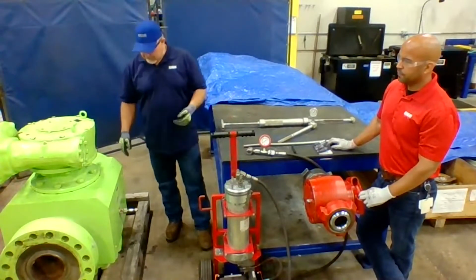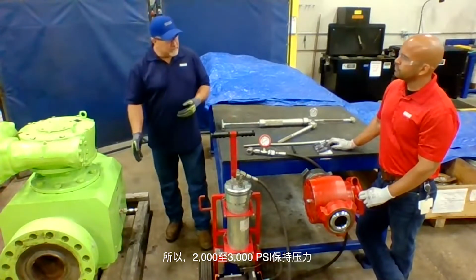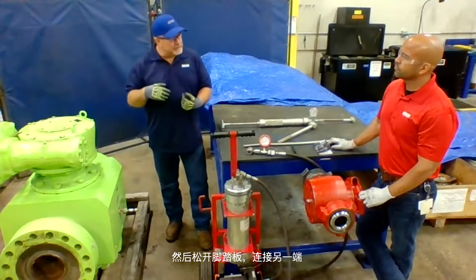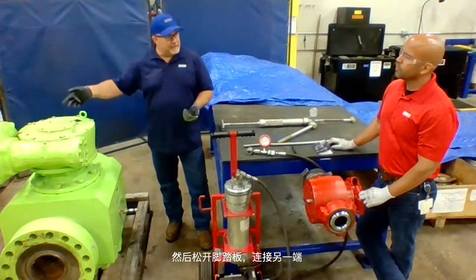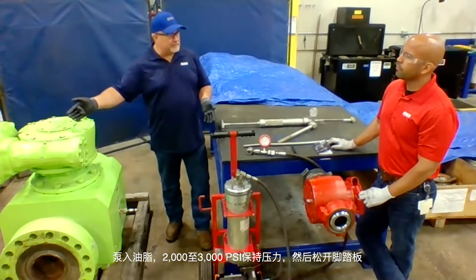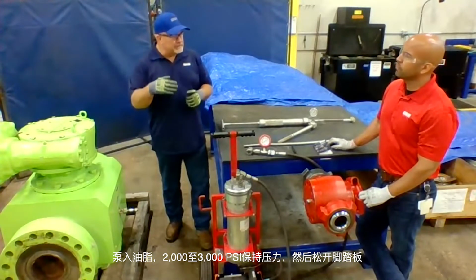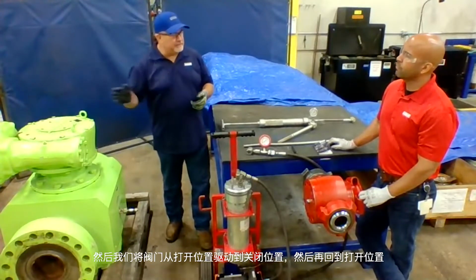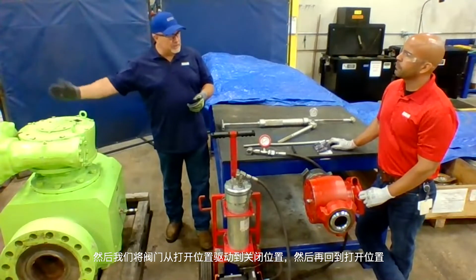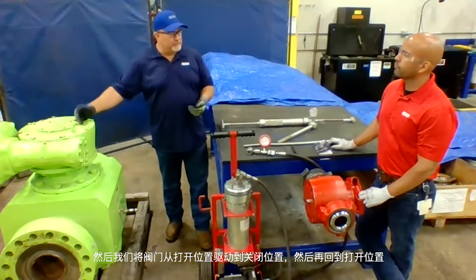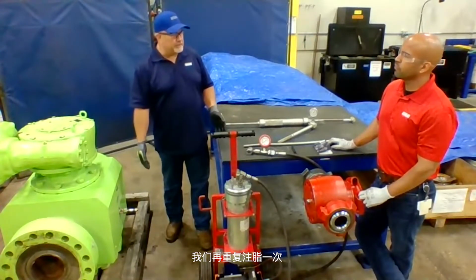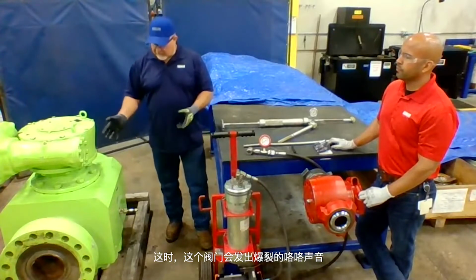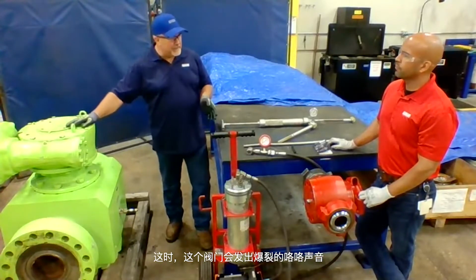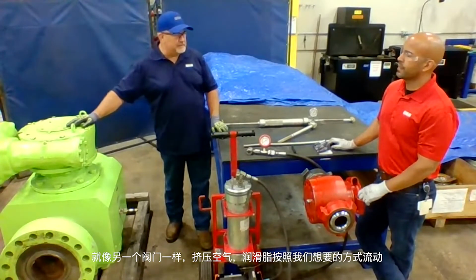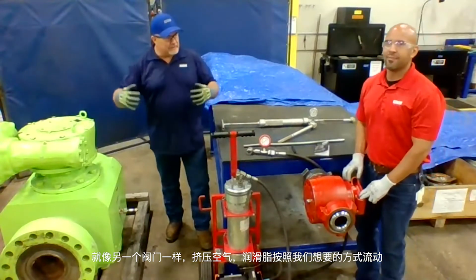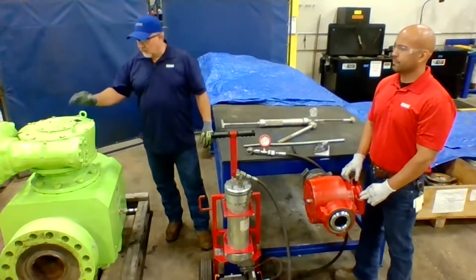Gotcha. So 2,000 to 3,000 psi, it holds pressure. We release, then we go to the other side, and we pump in 2,000 to 3,000 psi until it holds, release, and then we actuate the valve from open position to closed, and then back to open. And we repeat that one more time. At that time, this valve will pop and snap and gurgle just like the other valve does. Yeah, as air gets in there and the grease travels around the way we want.